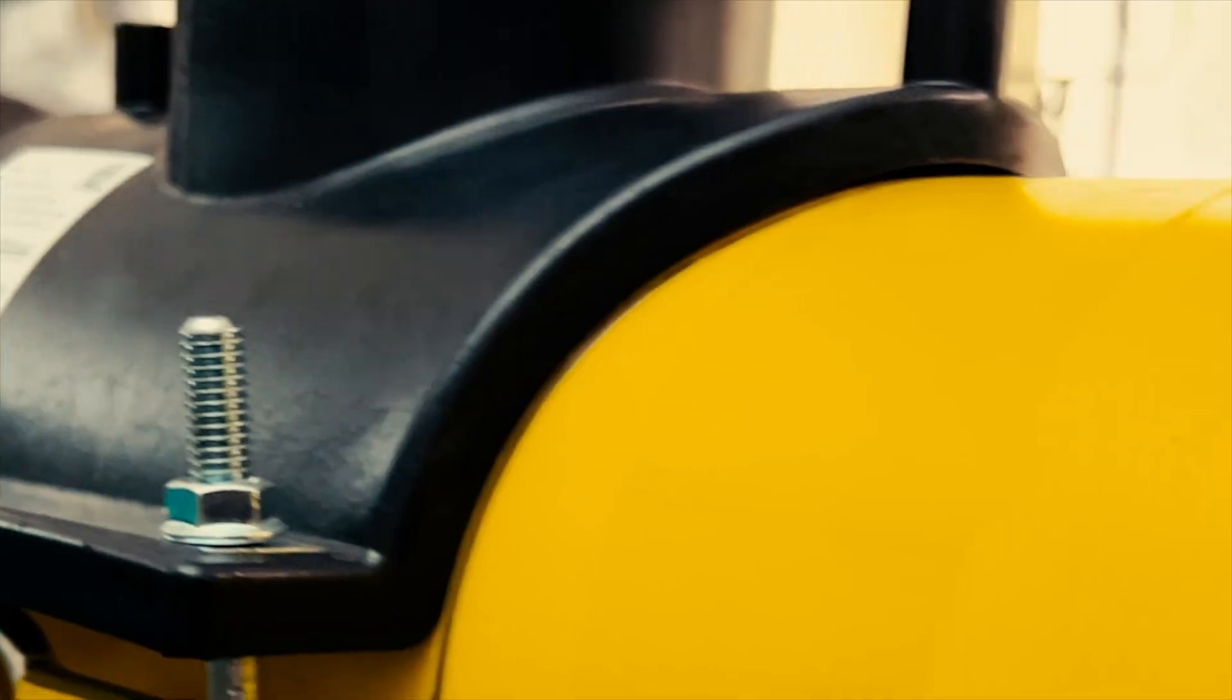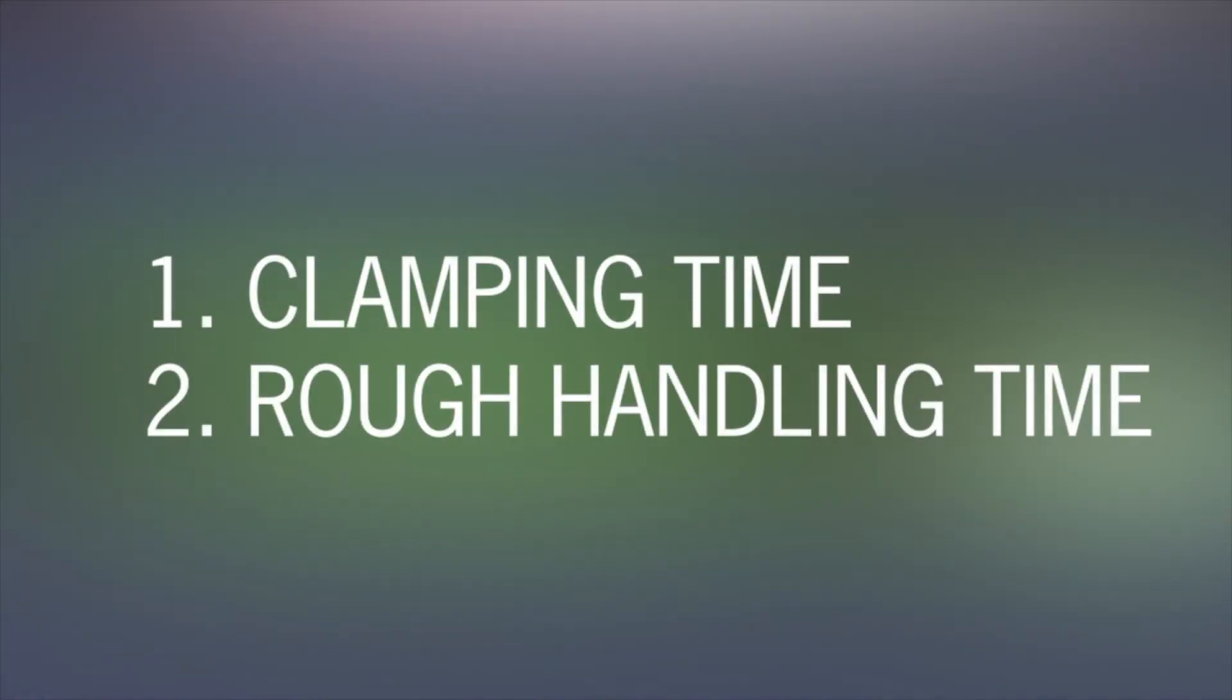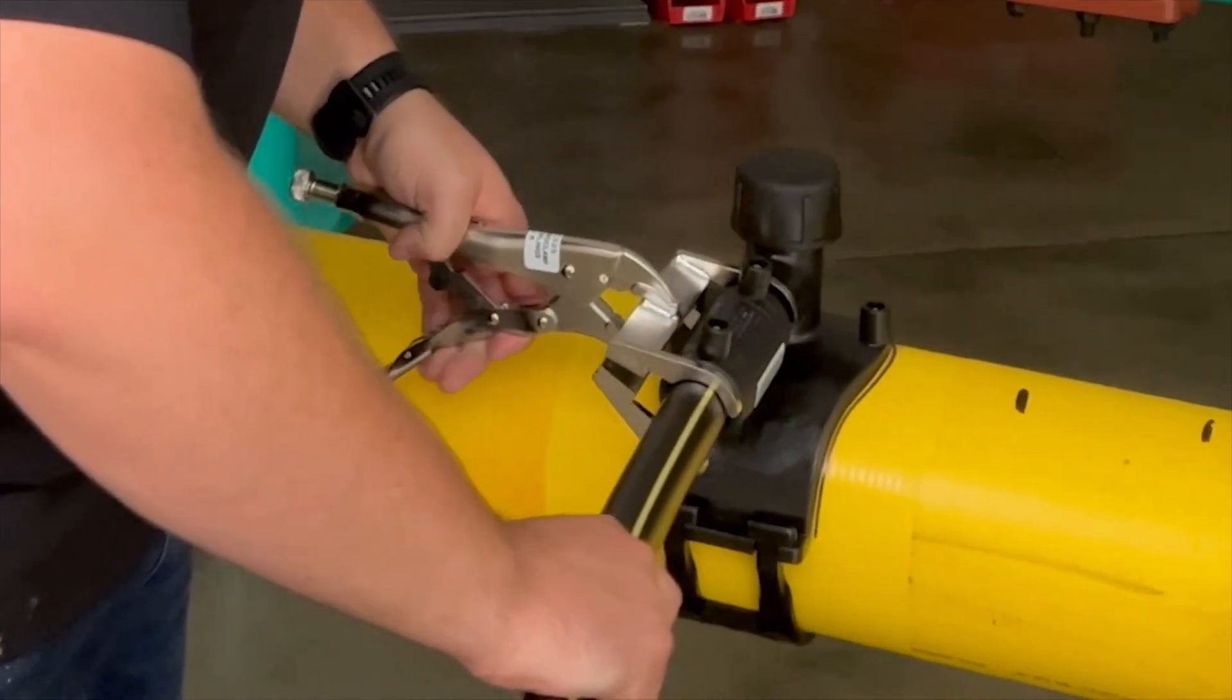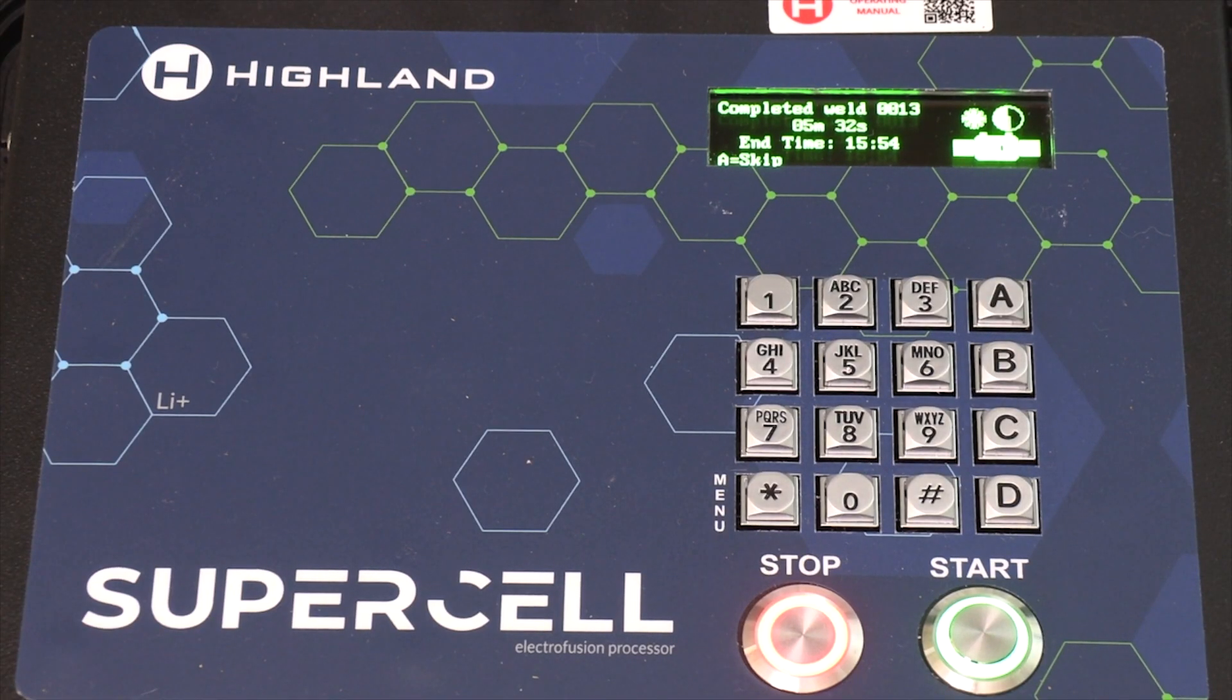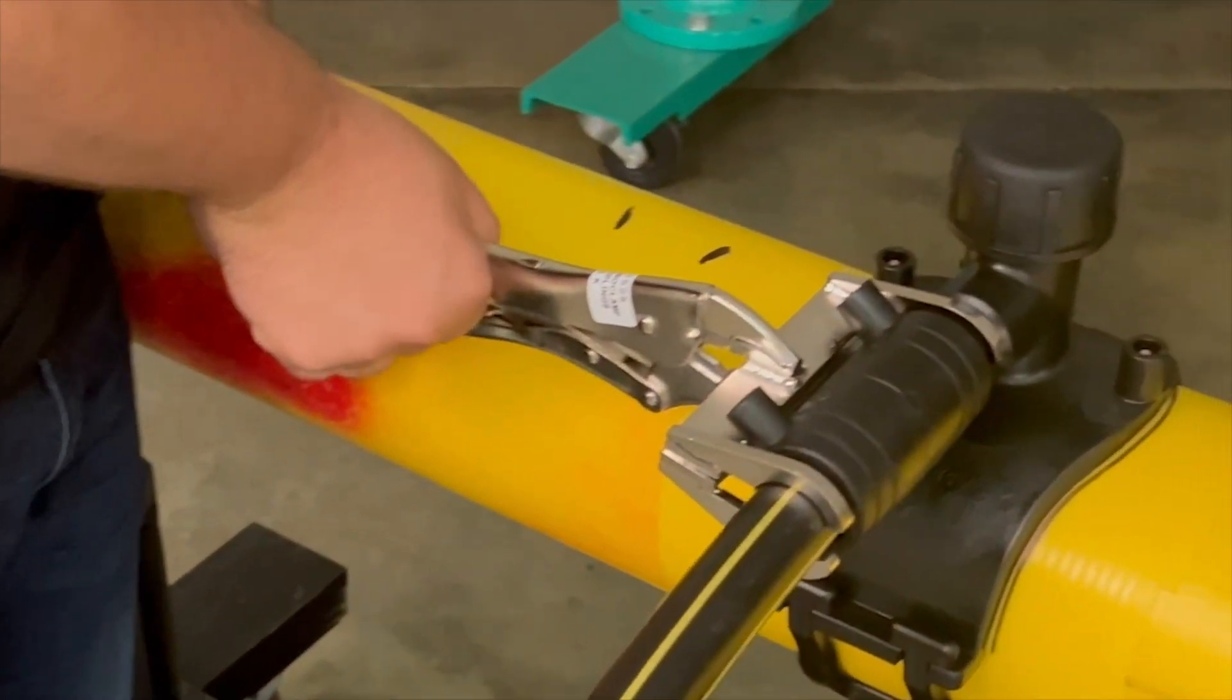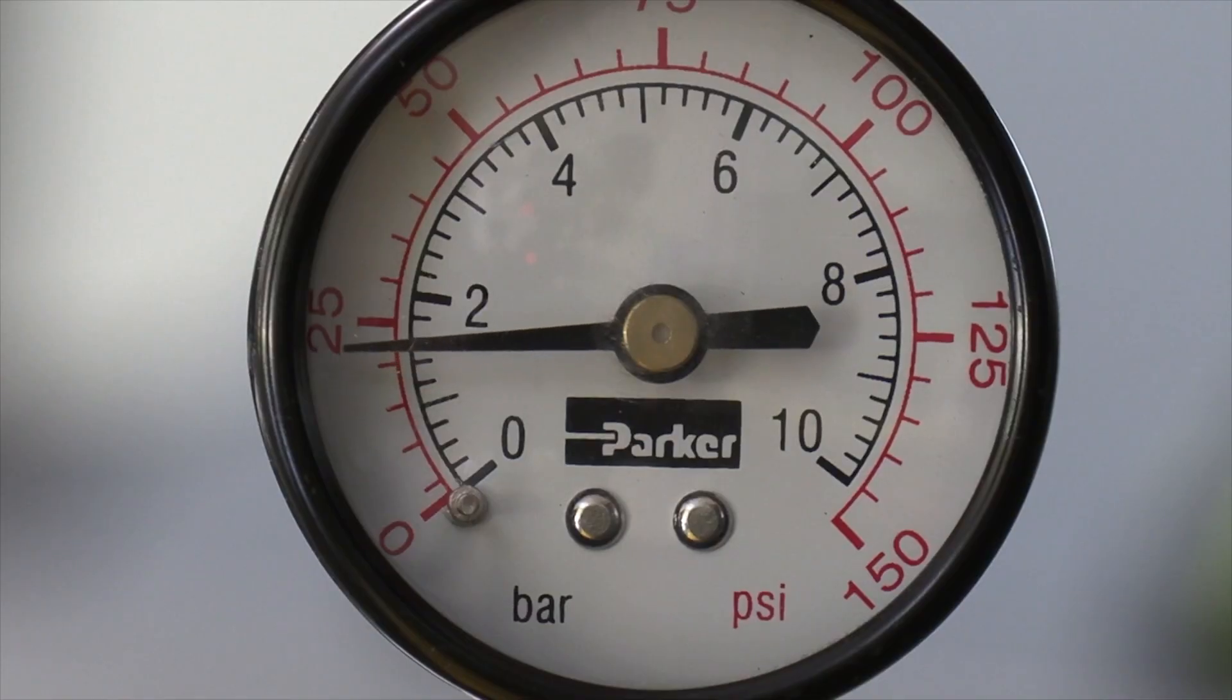Cooling any electrofusion fitting is a two-stage process starting with clamping time followed by rough handling time. Clamping time is listed on the fitting and is usually displayed by the processor. After clamping time is completed, the clamp can be removed from the fitting. Rough handling time is always longer and must elapse before performing pressure tests, tapping, backfilling, etc.